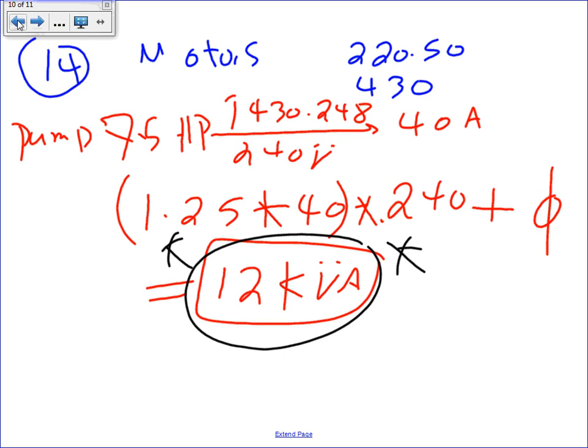When we're calculating the air conditioner and the heater, we pick the highest one. Right? And then I noticed on the previous one we did, we included the furnace in our motor load. How come we didn't include this? We didn't include the furnace in the motor load because it's not given as a motor load in this example, and we just lumped it in the heating. It's part of my heating system. Most of the time, guys, the furnace in particular would be part of the heating system, not standalone. It's included in the heating system. But if they give it to you, you throw in another motor here.